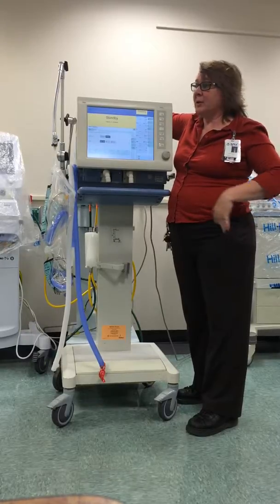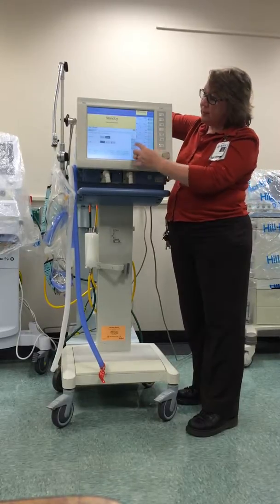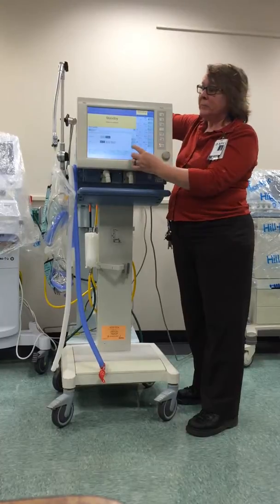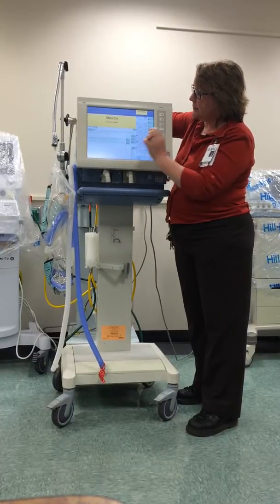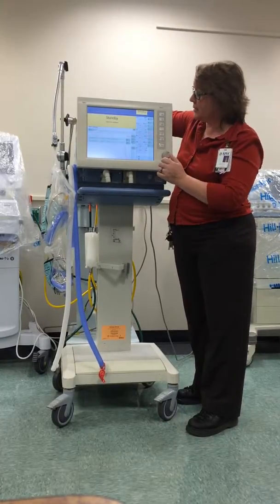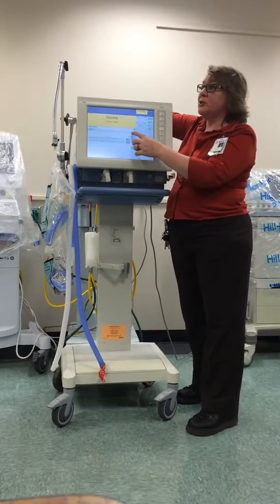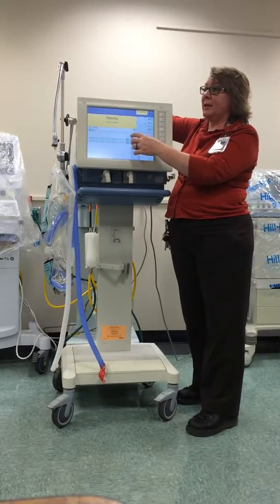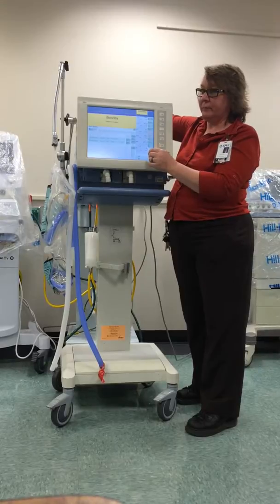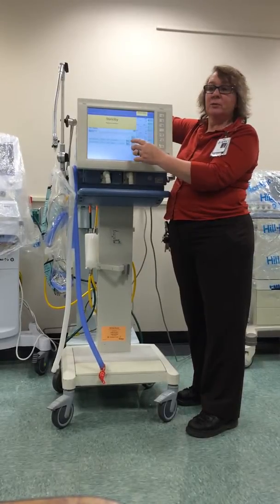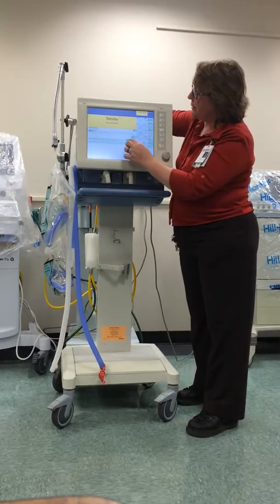So when you're ready to start the calibration, there are some little tabs over here to the side. You're going to hit the one that says check because we want to do our checkout procedure. And then under here are two different checks: a device check and an airtight check. So you have to do them both. The first one we're going to do is the device check.